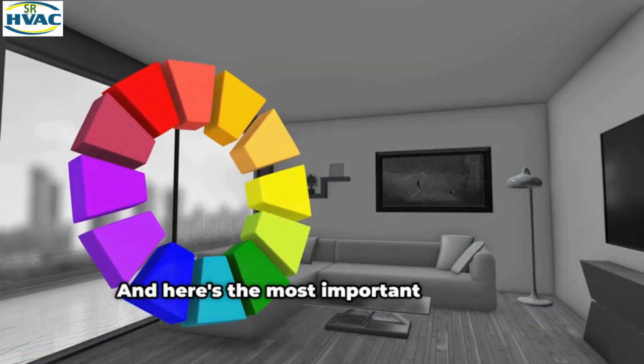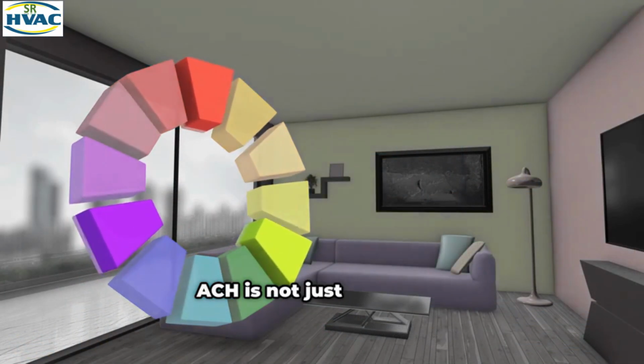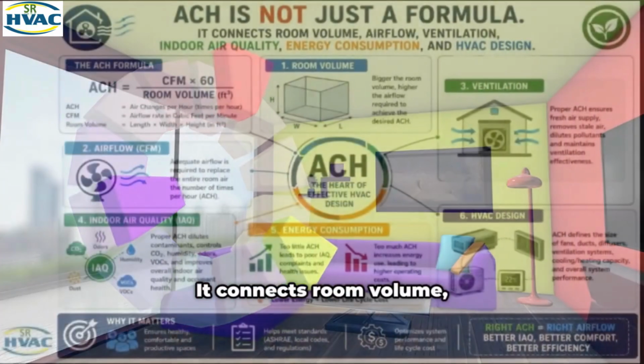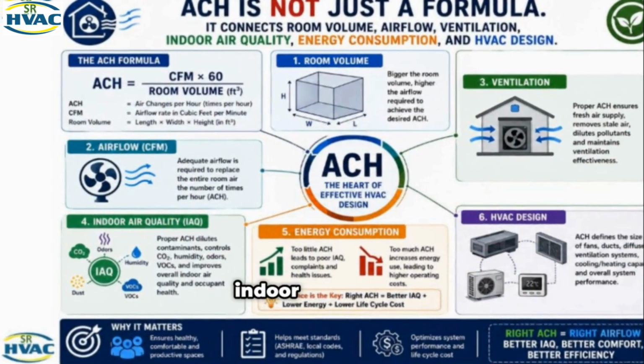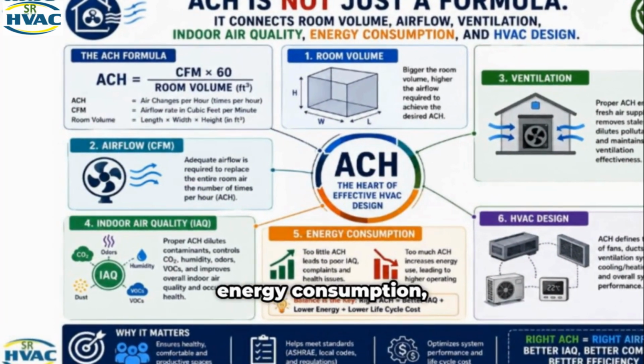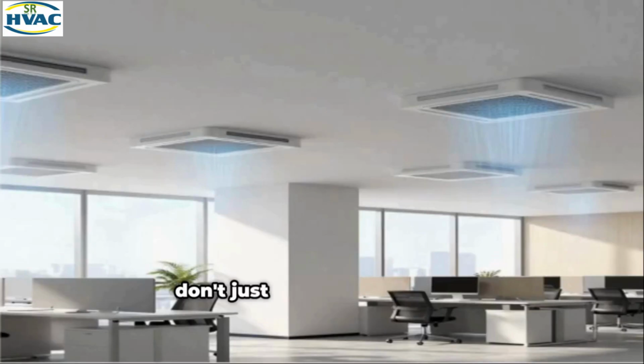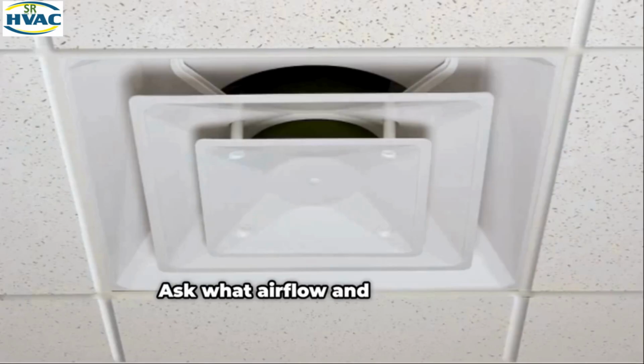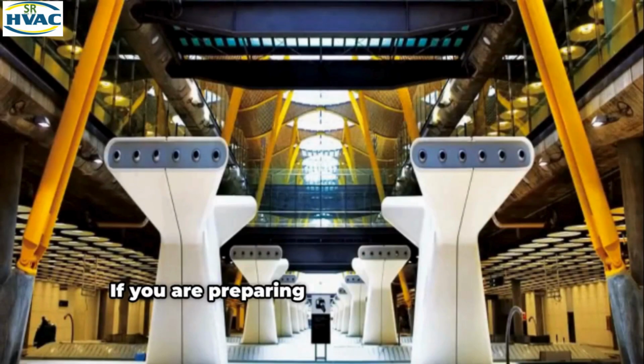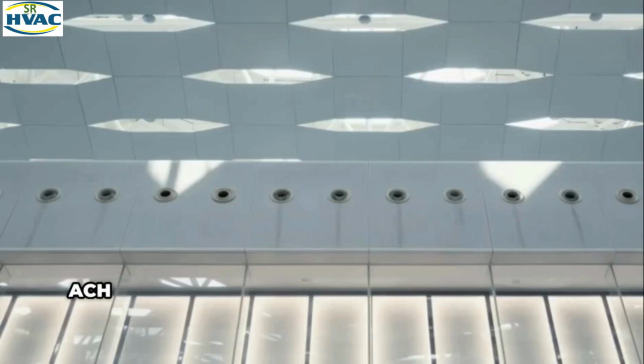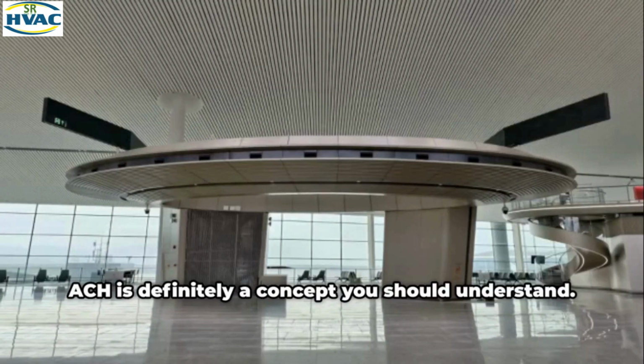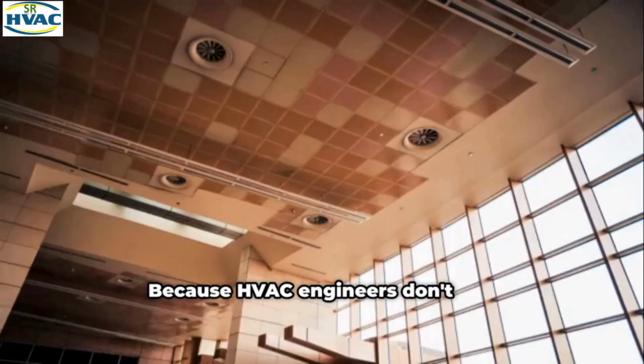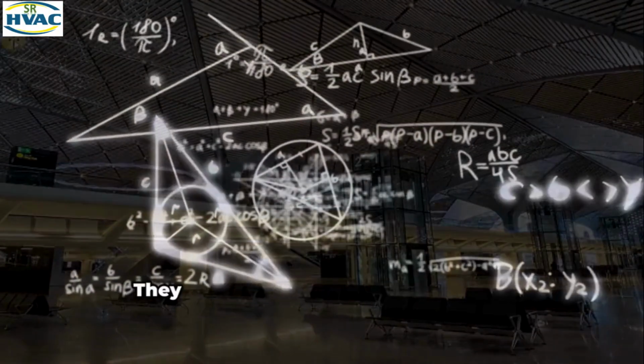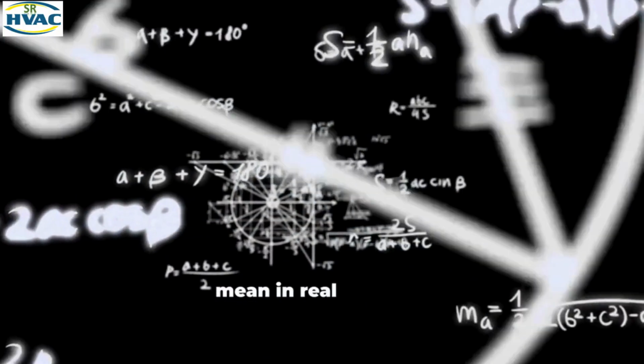And here's the most important takeaway. ACH is not just a formula. It connects room volume, airflow, ventilation, indoor air quality, energy consumption, and HVAC design. So whenever you see an ACH value, don't just look at the number. Ask what airflow and application produced it. If you are preparing for an HVAC interview, ACH is definitely a concept you should understand, because HVAC engineers don't just memorize formulas, they understand what those formulas mean in real systems.